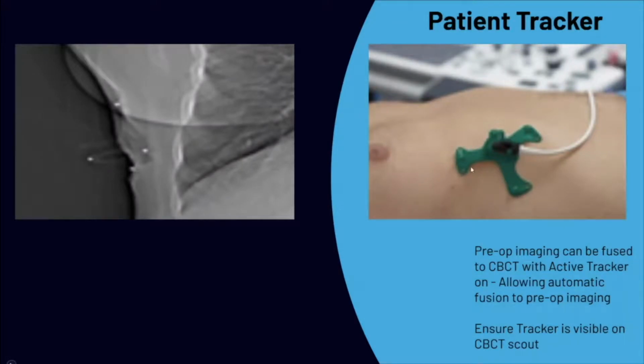This is the fiducial marker that's taped to the patient's skin. It's got a couple of markers that can be identified on the cone beam CT like this, and then it attaches at the top to a probe that connects through its magnetic tracking system to know the position of the body and where all the other elements are. Notably, the ultrasound probe has a connection to the system. And then there's a needle guidance probe that either clips on the back of the needle, or they have a small fiber that will fit down a guiding cannula.